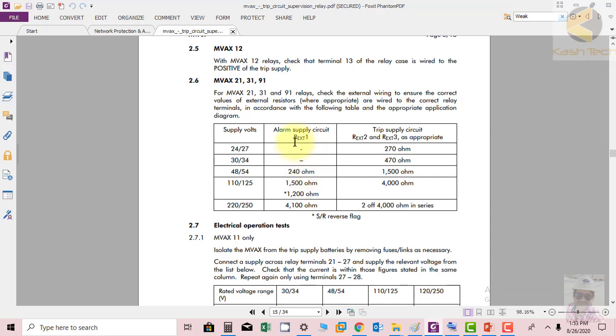This applies to the alarm supply circuit. But as I told you, for the trip circuit you can see at each level they have provided a separate resistor. This is just for safety purposes, so that if the coil of the trip circuit supervision relay itself is short circuited, it will not even in that case trip the breaker.